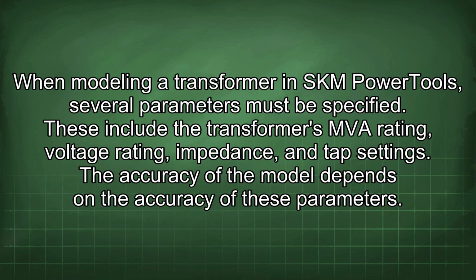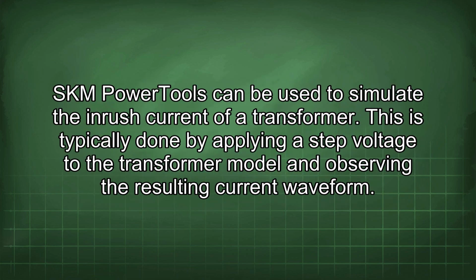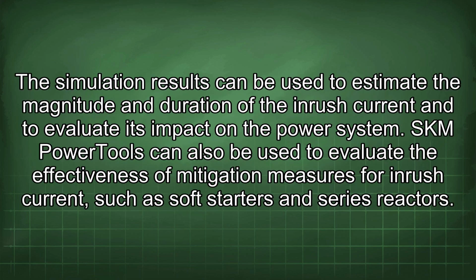When modeling a transformer in SKM Power Tools, several parameters must be specified. These include the transformer's MVA rating, voltage rating, impedance, and tap settings. The accuracy of the model depends on the accuracy of these parameters. SKM Power Tools can be used to simulate the inrush current of a transformer. This is typically done by applying a step voltage to the transformer model and observing the resulting current waveform. The simulation results can be used to estimate the magnitude and duration of the inrush current and to evaluate its impact on the power system.